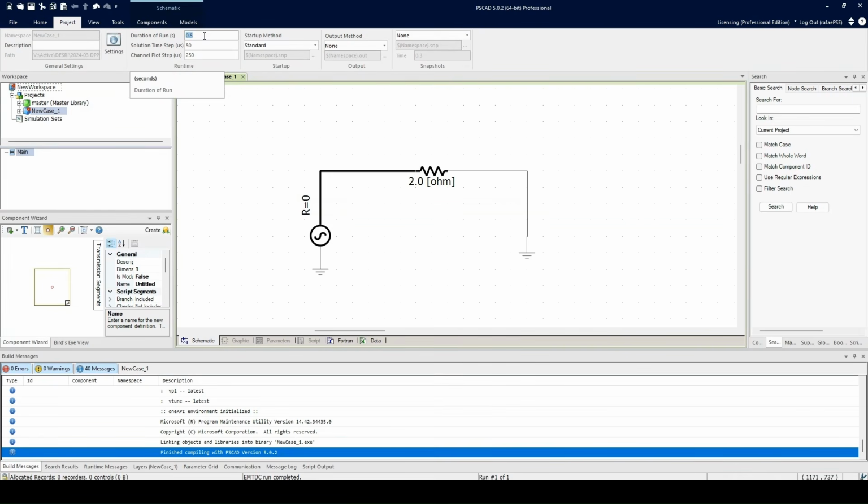Generally speaking, when we're performing any sort of IBR testing or IBR model development, we set this to about a 30 second run. That's how long, generally speaking, your tests are, 30 to 40 seconds. They could be 10 seconds depending on the situation or what you're testing. But just for the sake of this particular example, I'm going to set this to 500 so I can make a point of what I'm trying to say.